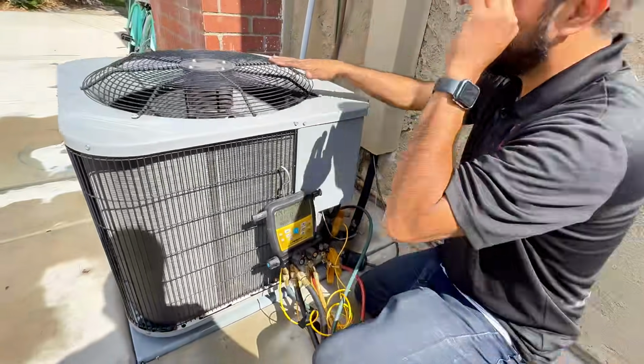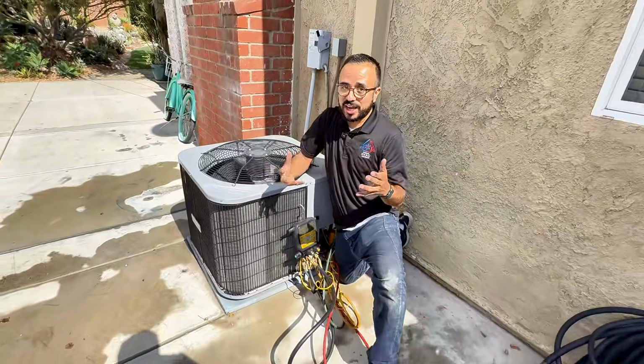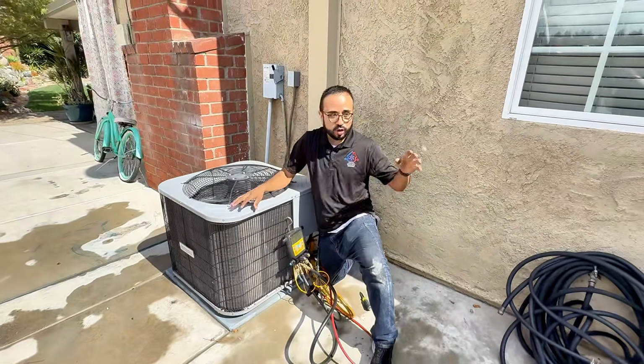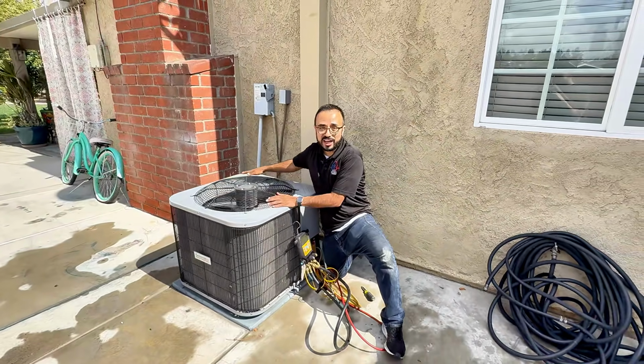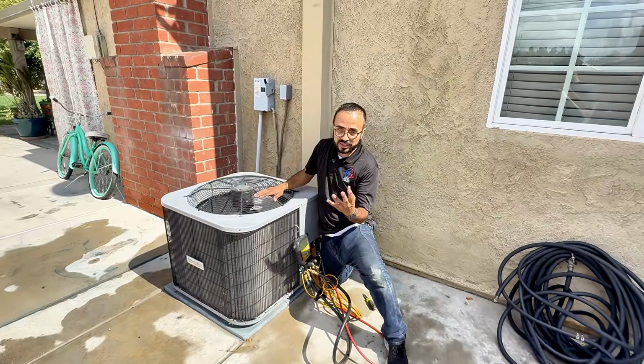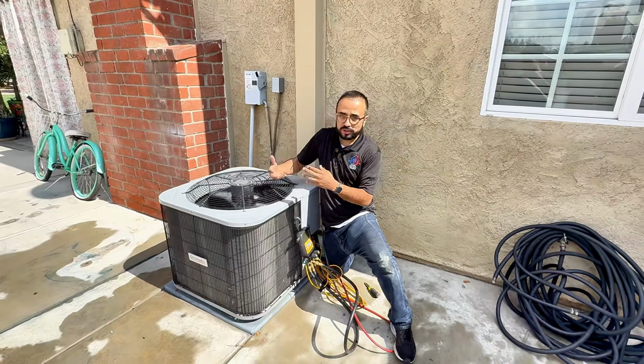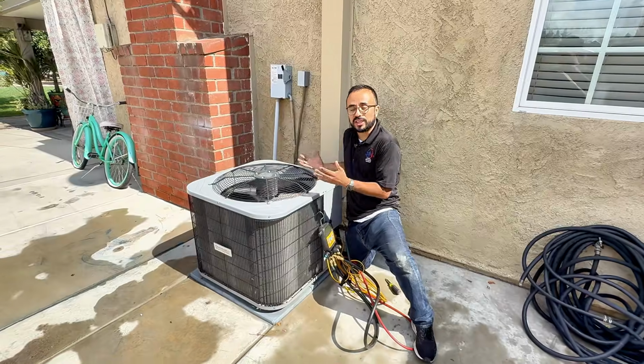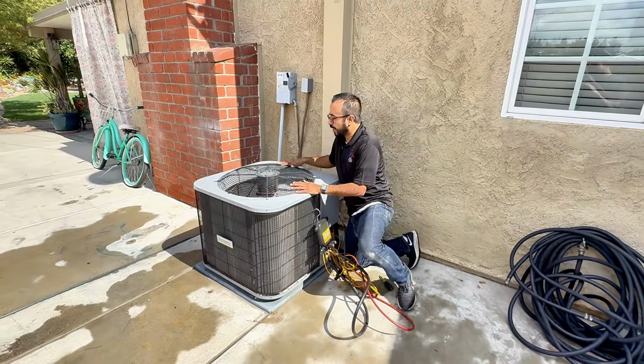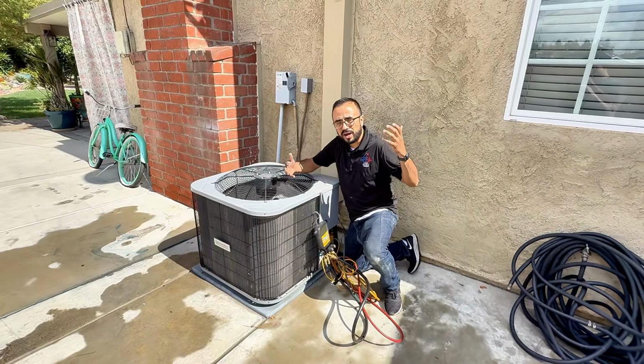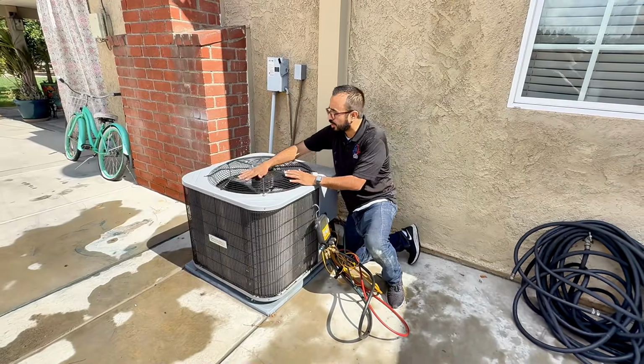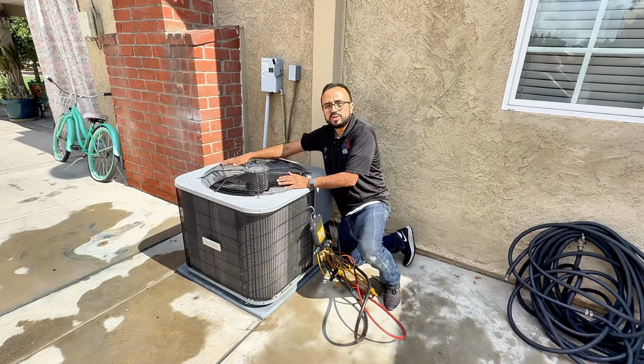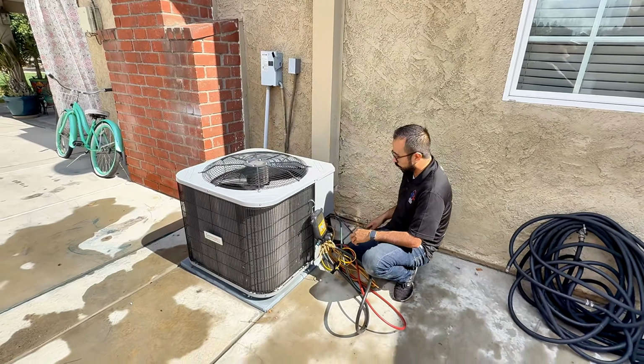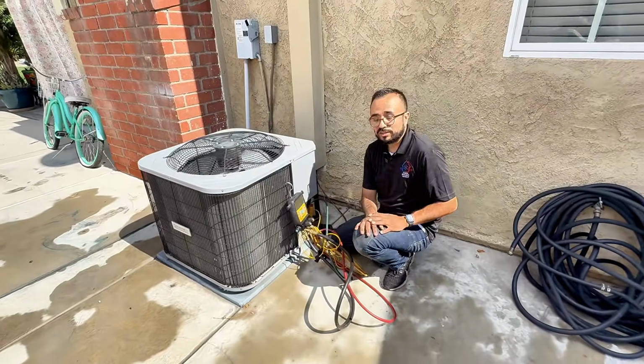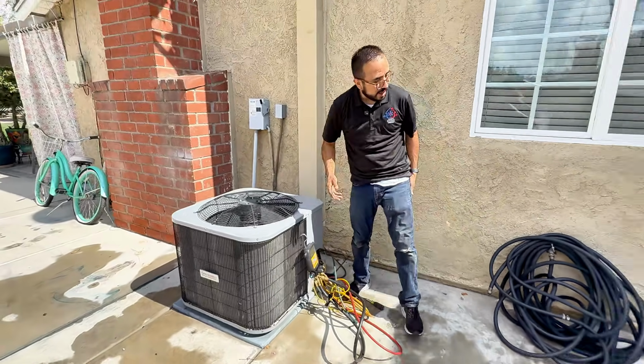And you can tell if a system is okay on a hot day: if it's hot and you're calling for cooling and this is not hot, you've got an issue. Because on a hot day, when you're trying to cool the house, this should be pretty hot because you're rejecting a lot of heat. But the house isn't too hot inside, it's about 74 degrees. So it's hot, but it's not too hot, right? So I like what I'm seeing. Let's go ahead and get our delta T.